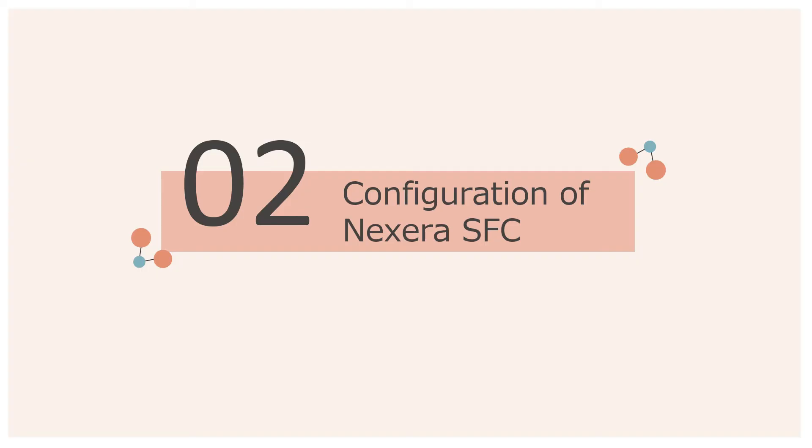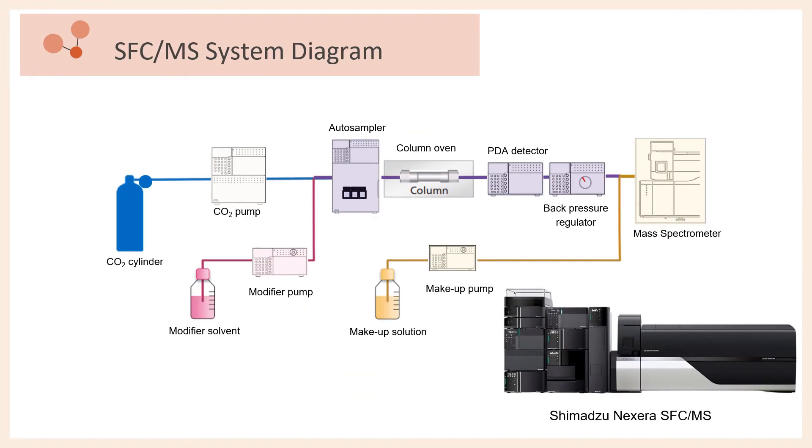We will now move on to the configuration of Nexera SFC. Here we can see a diagrammatic overview of a SFC system coupled with a mass spectrometer detector. The mobile phase is delivered from a pump which draws carbon dioxide from an external gas cylinder. If needed, the carbon dioxide mobile phase may be mixed with polar modifier solvents to adjust the polarity. The sample from the autosampler then mixes with the mobile phase, enters the column, undergoes separation, and finally enters the PDA detector. Depending on the detector required, either the PDA or MS can be used, if not both. A back pressure regulator is positioned downstream the PDA detector to maintain the pressure of the flow channels by opening or closing valves in response to any pressure fluctuations. The presence of a back pressure regulator hence prevents the vaporization of the supercritical carbon dioxide mobile phase and keeps it in a supercritical state.